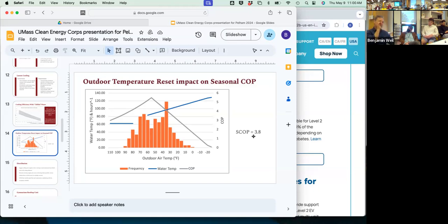Now, if we get the water temperature exactly right, that's not going to happen very much because it's always going to just keep up with the load. But nothing's perfect, right? So there's a reasonable chance that the fans are actually quiet. And one approach is to actually, whatever speed they're on, turn it down to a lower speed. Because now it's quieter, but now, of course, we've got less resistance that we're capable of overcoming. So there's a trade-off between filtration and noise. And I would suggest, I don't know this, but I would rather do the air quality with the big ventilators on the roof and keep the filtration at the MERV 8, get the noise benefit instead. But it's a trade-off, and if you had people complaining about pollens, you could bump them up.